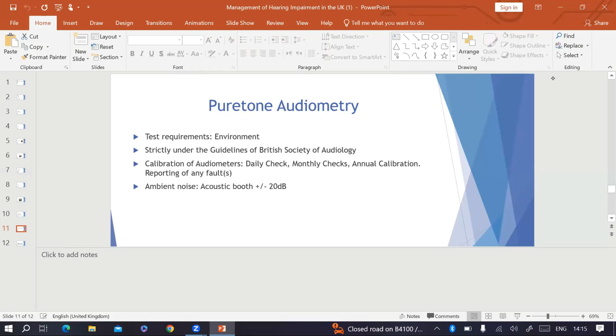And for the opinion, if they still think they will benefit from hearing aids, then we have to do that. Pure tone audiometry is the main test done to assess sensory hearing in old age. The test requirements are a comfortable environment with no activity, strictly under the British Society of Audiology's guideline. Calibration of audiometers: daily check, monthly check, and annual calibration should be done. Any faults should be reported. Ambient noise level should ideally be about 20 dB.